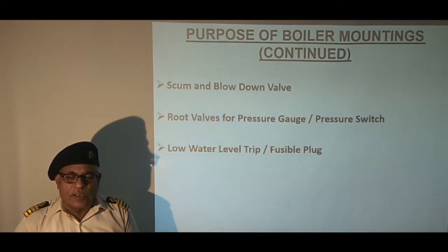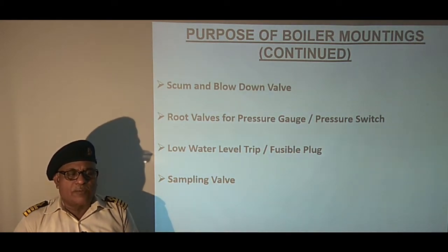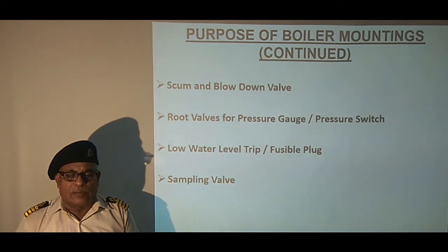Fusible plug, on the other hand, was used on earlier smoke tube boilers to prevent the damage to the boiler when firing with low water level by admitting the steam in the furnace and extinguishing the fire. Next is sampling valve. This valve is used to draw the boiler water sample for testing purpose through a cooler.